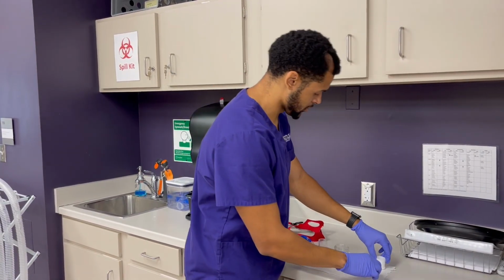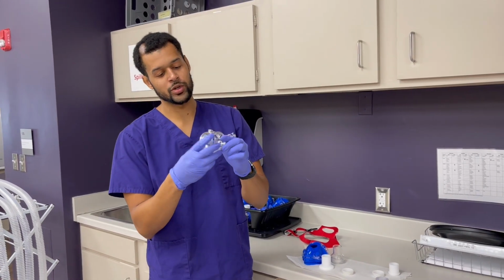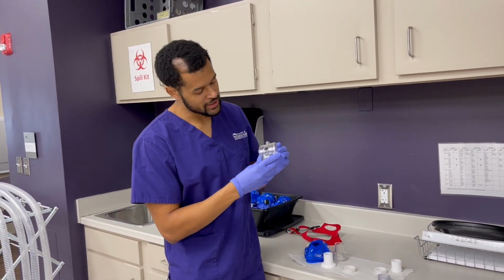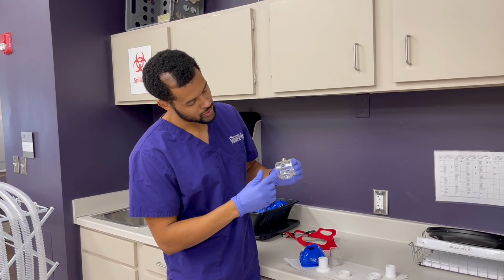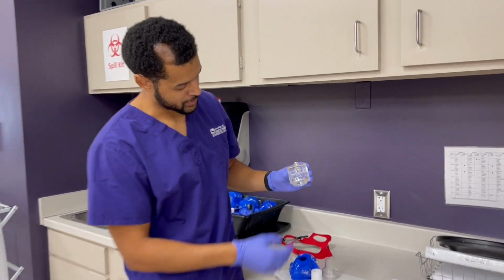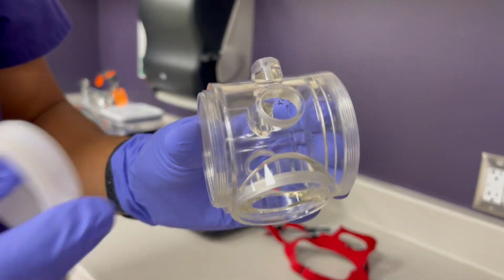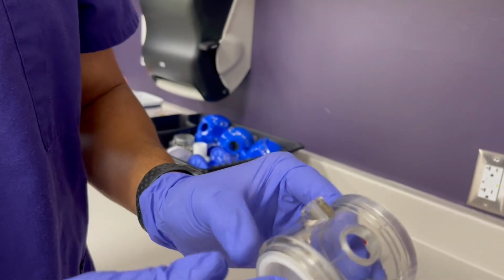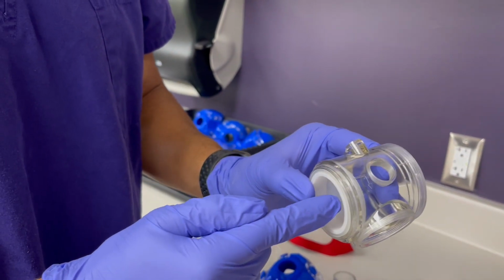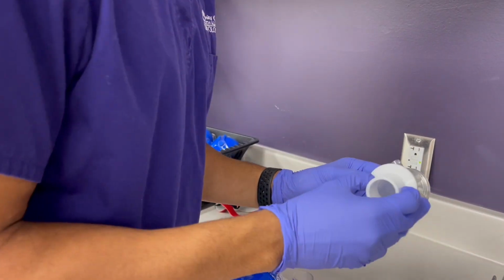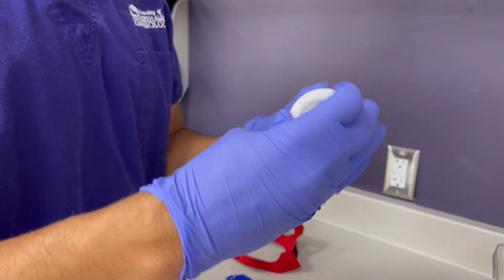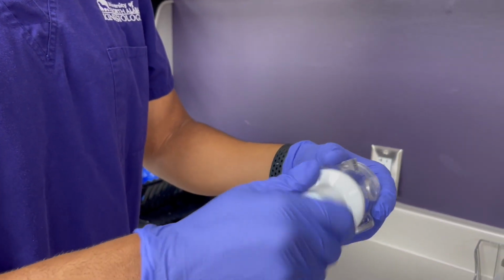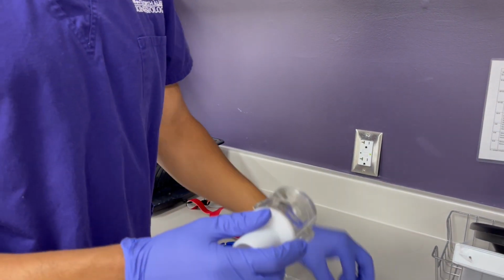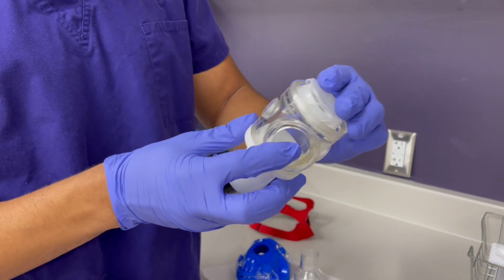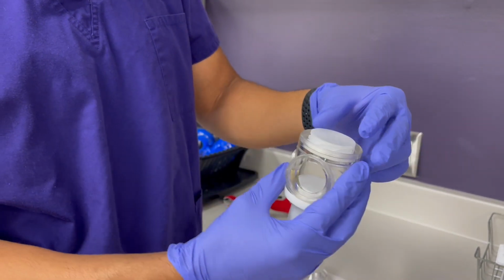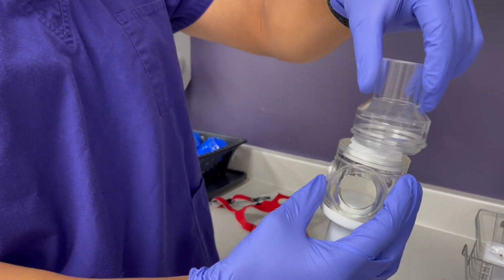So when you're putting the mask together, first thing you're gonna do is you're gonna grab the base piece, and on this base piece there's actually two different arrows, and so each arrow explains to you where the valve needs to go. And so this valve will go in here, and so one quick check is making sure that the valve goes the same direction that the arrow goes. And then once that's the case, you'll screw in the more white valve to it. Next, on the other side, making sure that this is the valve that goes out. So you'll put it down and this one kind of just sits in there, and then the clear one goes on the outside.